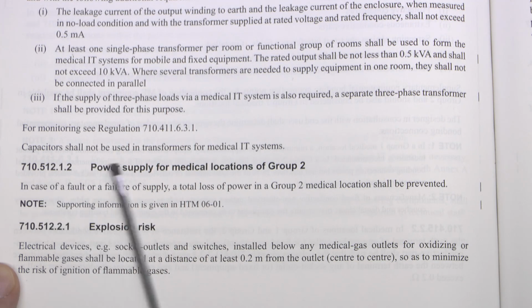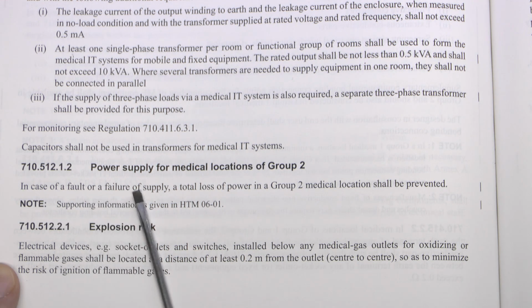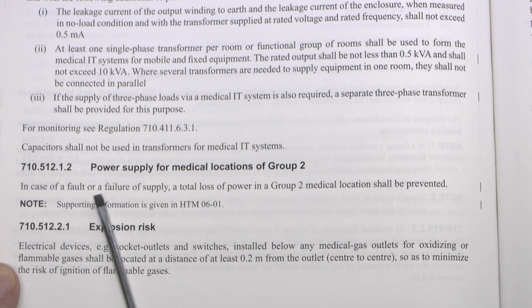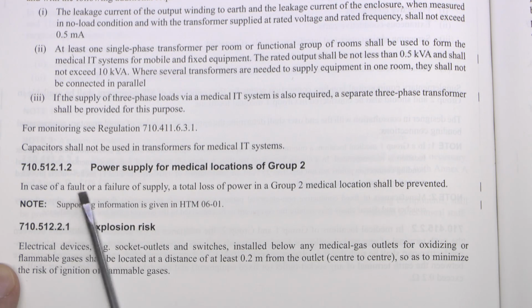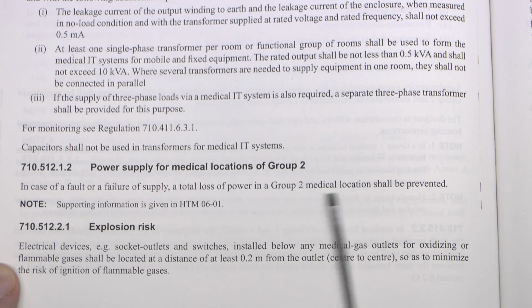710.512.1.2. This existed before, but it's been changed. It now says, in case of a fault or failure of supply, previously it actually stated first fault to earth. So a slight rewording of that, as in fault or failure of supply, not necessarily first fault to earth. And continues as before, a total loss of power in a Group 2 medical location shall be prevented.